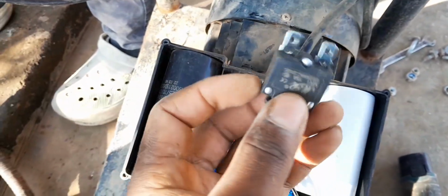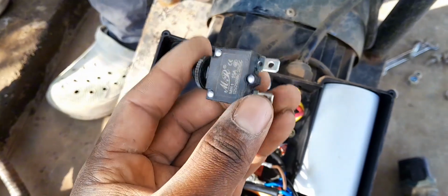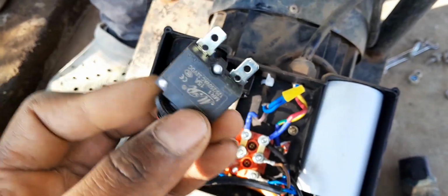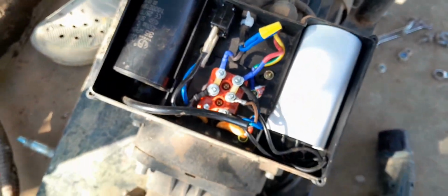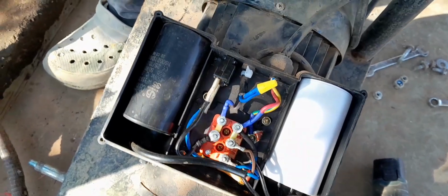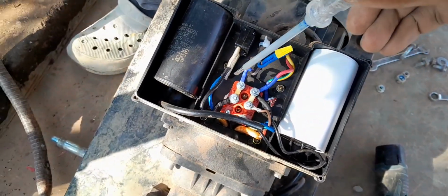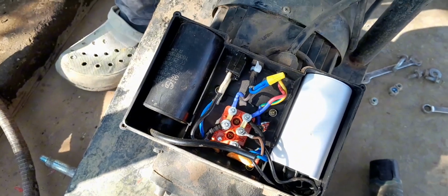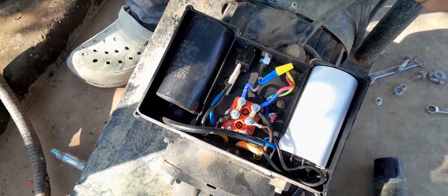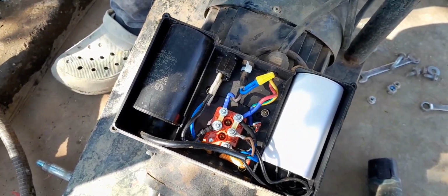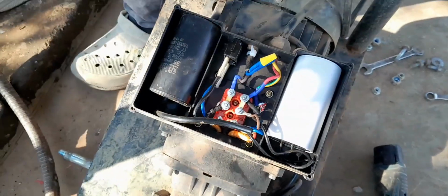After we installed it, the system did not work. So the next step is to check whether there was continuity between the motor and the live or neutral cables, and there was none, which means that the motor is working correctly or should be working correctly.